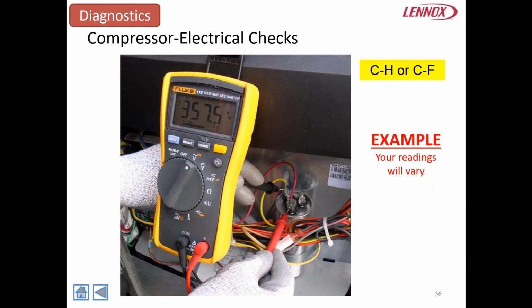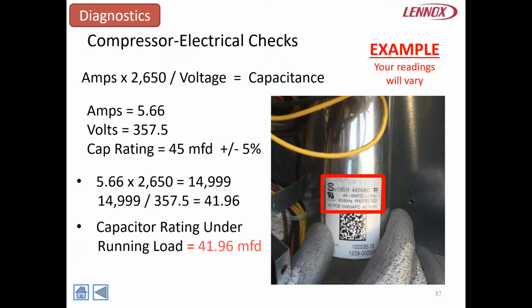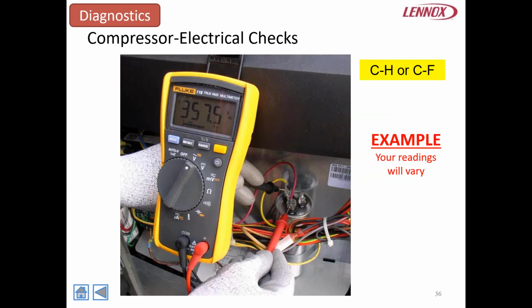With the unit still operating, we want to measure the voltage again between HERM and common. In this example, we get 357.5 volts AC. So all we do is take those two numbers, we take our amp draw of that lead, and we take our voltage of that lead. And I want to back up here just a second to this slide. Notice that the voltage is always going to be much higher than the 230, 240 volts that you're used to working with. If you notice on the side of a capacitor, it's rated for 370 volts or even 440 volts. And that's the reason why.